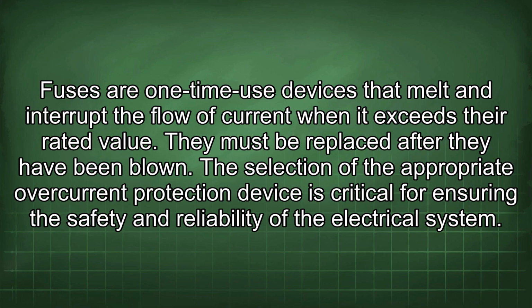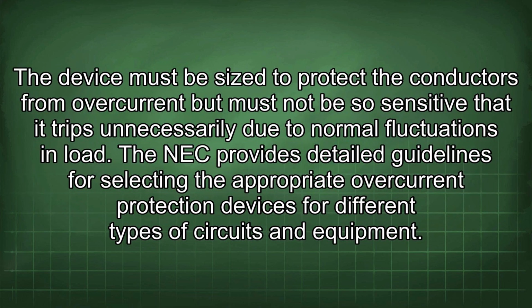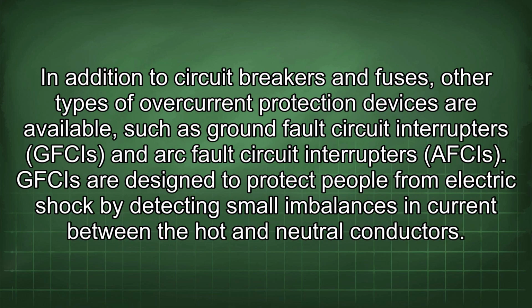The selection of the appropriate overcurrent protection device is critical for ensuring the safety and reliability of the electrical system. The device must be sized to protect the conductors from overcurrent, but must not be so sensitive that it trips unnecessarily due to normal fluctuations in load. The NEC provides detailed guidelines for selecting the appropriate overcurrent protection devices for different types of circuits and equipment. In addition to circuit breakers and fuses, other types of overcurrent protection devices are available, such as ground fault circuit interrupters (GFCIs) and arc fault circuit interrupters (AFCIs).